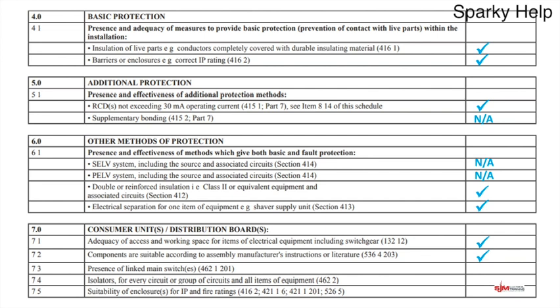Presence of a linked main switch. Well, what are we talking about there? Well, we'll tick it because it will be there, this is your main switch in your consumer unit. Depending on your earthing system and whether it's single phase or three phase will determine whether it's 2-pole, 3-pole or 4-pole. So you'd need to go and look at 462.2. But all domestic installations, single phase, and all single phase in general, you would make double pole, but it's more about who's able to switch it, why it is. So it's double pole in all cases.